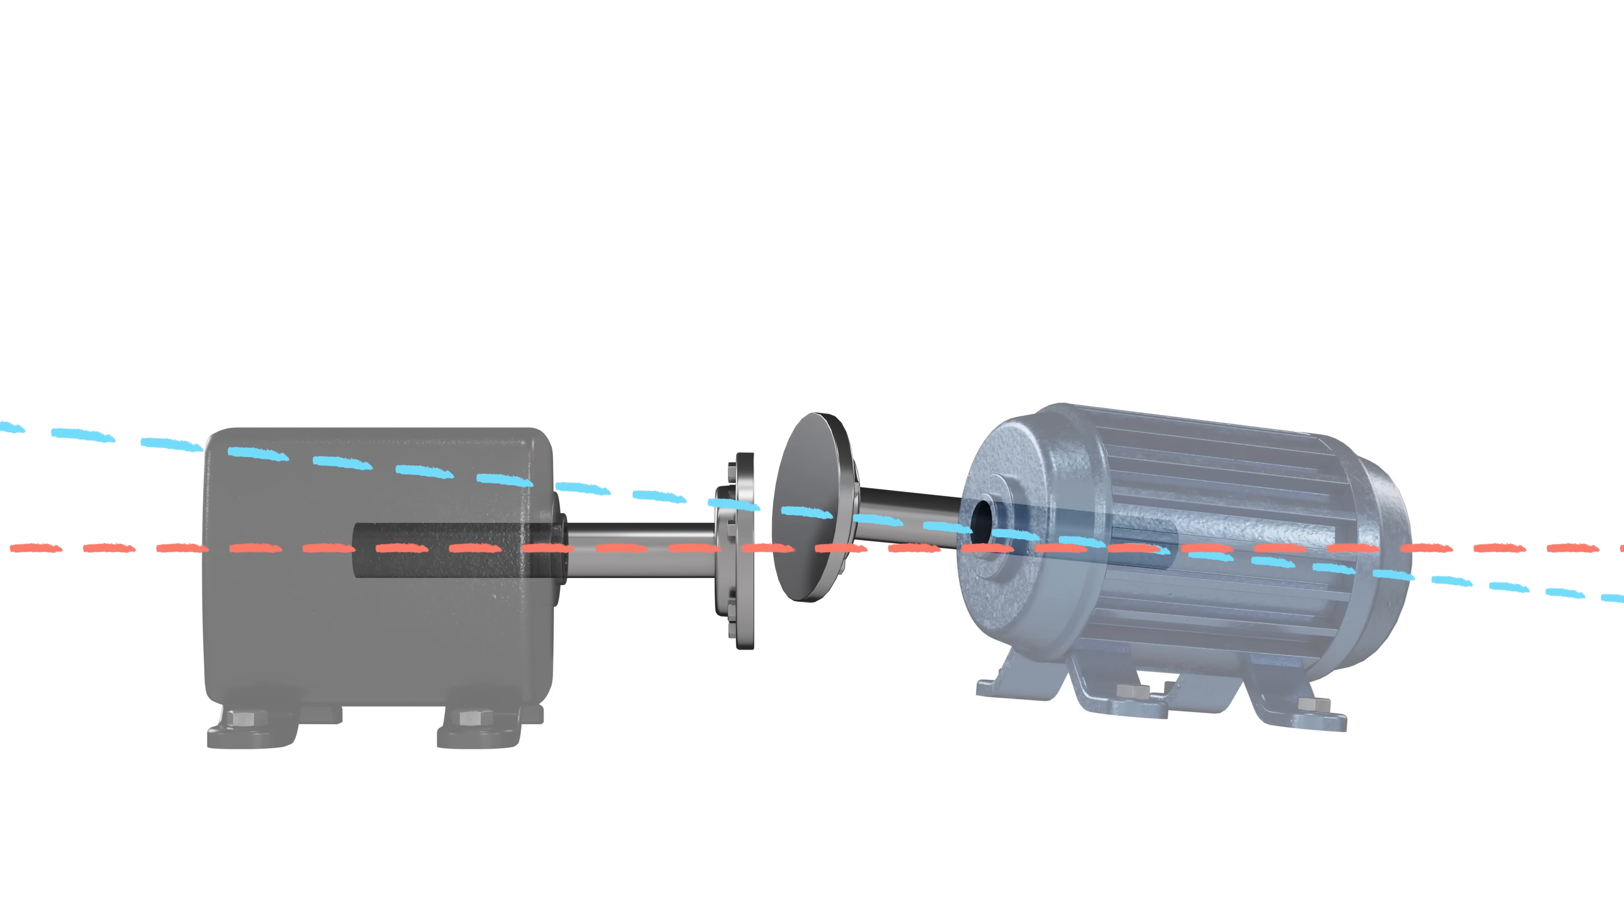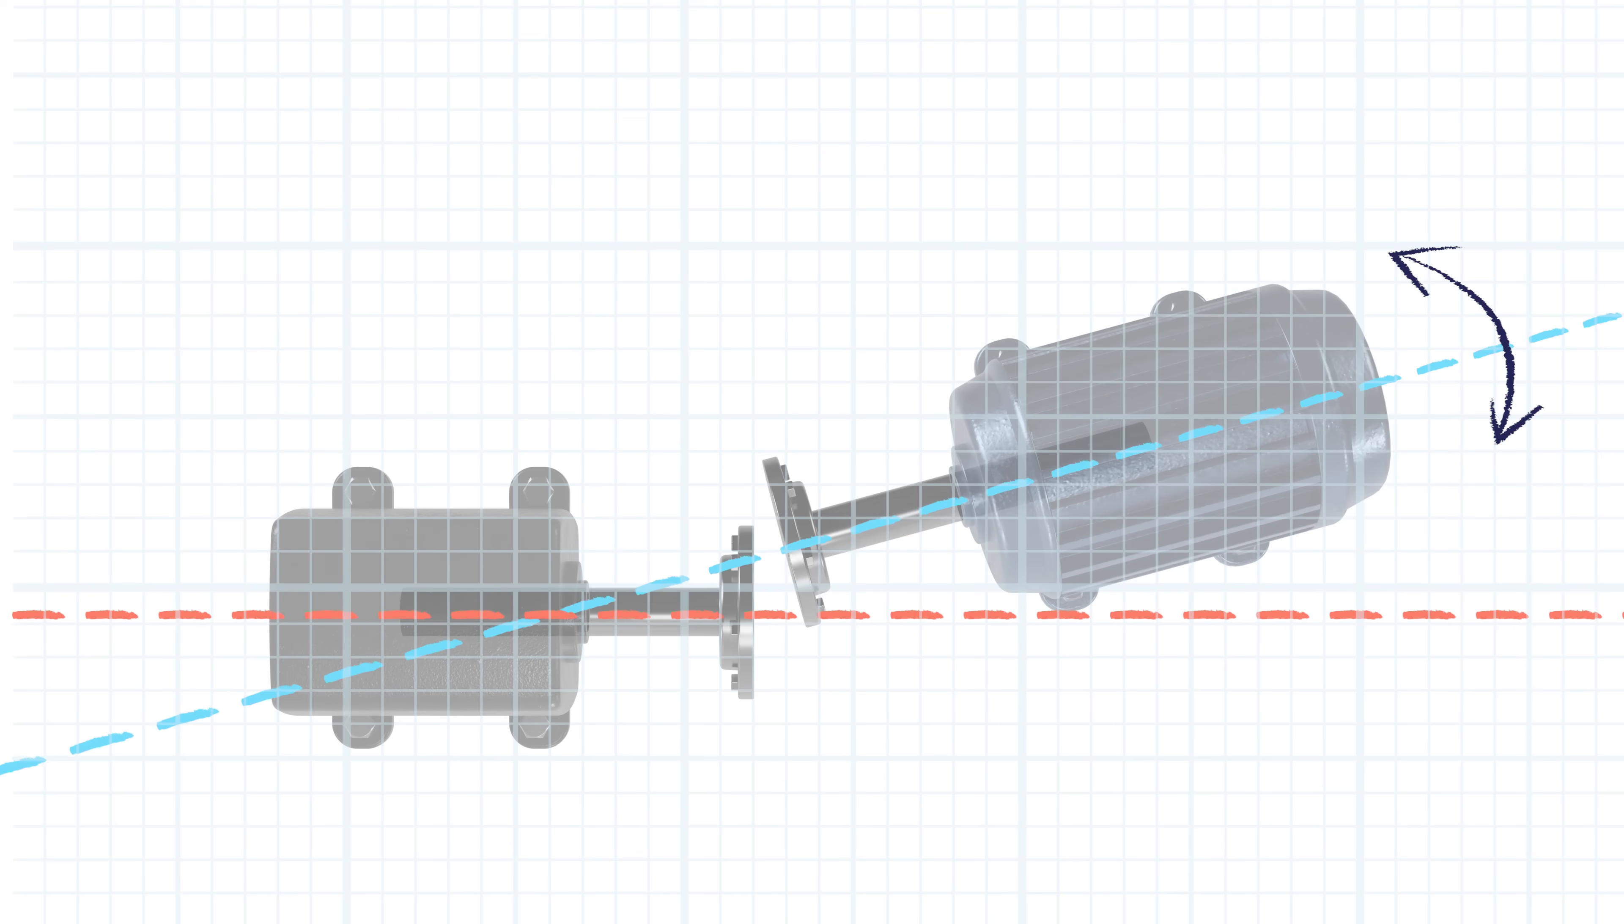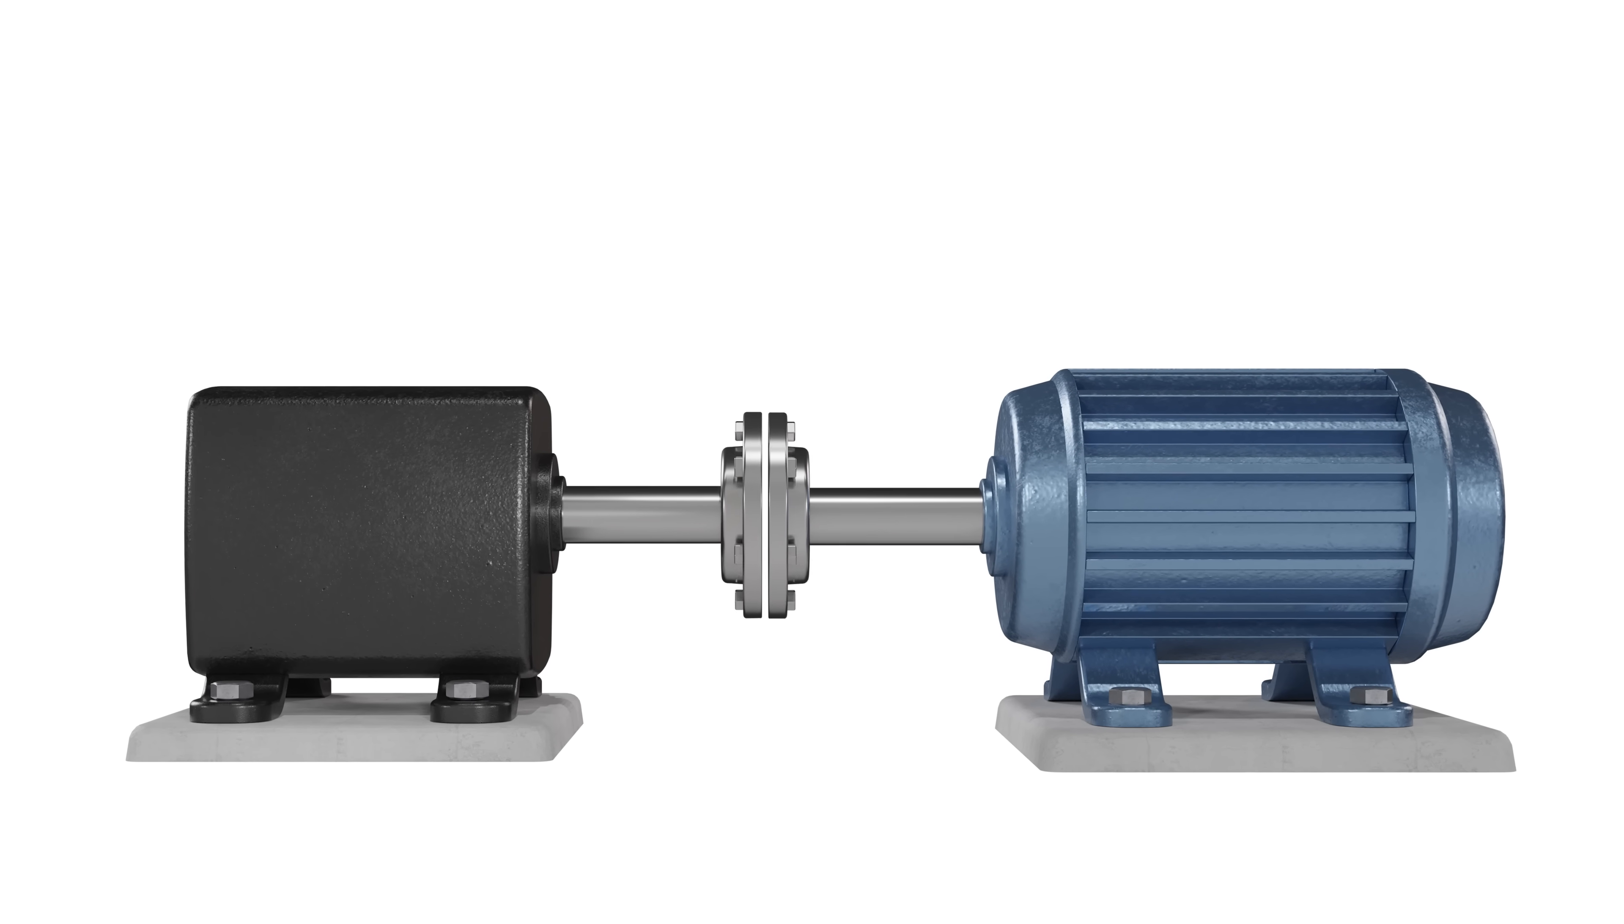Fortunately, we are able to adjust the relative position of the two shafts in these two dimensions. We can raise or lower the movable machine in the vertical plane and we can move it side to side in the horizontal plane. If we get the shafts aligned in these two dimensions or planes, they will then be in tolerance and close to collinear.